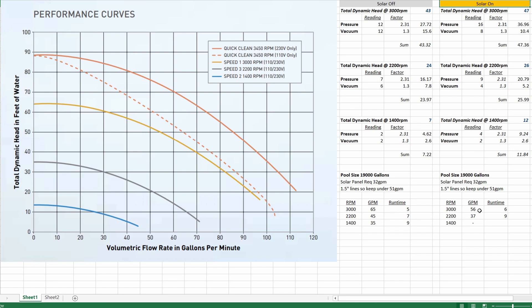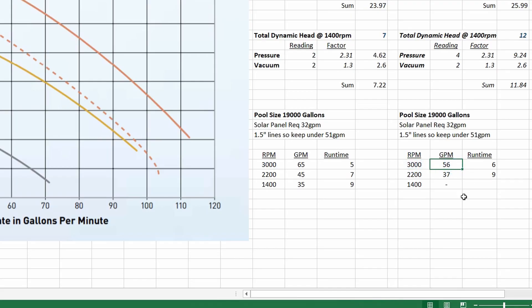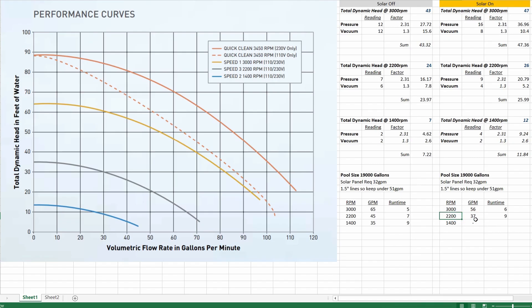So at 3000 RPMs with the solar on I actually lost about 10 gallons per minute but at 1400 RPM it couldn't get it up to the roof so 1400 RPM is too low for it to work with solar turned on but 3000 RPMs again is giving me still over 51 gallons per minute so that's still too fast on the RPM side of things so I'd want to slow down the pump which is fine because that actually uses less electricity which is good for me.